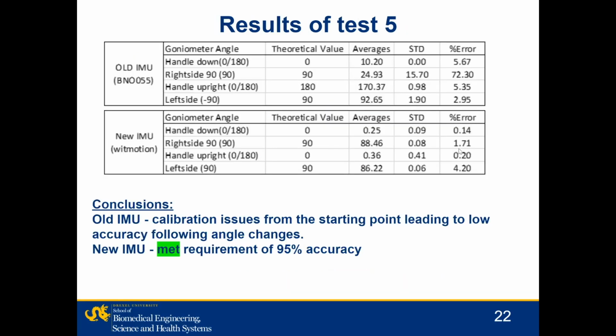The top table is the Old IMU, which did not meet the requirement of accuracy. You can see that the percentage error is greater than 5%. And interestingly, the right side angle of 90 degrees is off by 72%, where the angles are drifting away from the predetermined angle of 90. The bottom table is the new IMU data from the WitMotion sensor, where the percentage error is within the 5% margin required, and it was concluded that the new IMU is more accurate than the Old IMU.